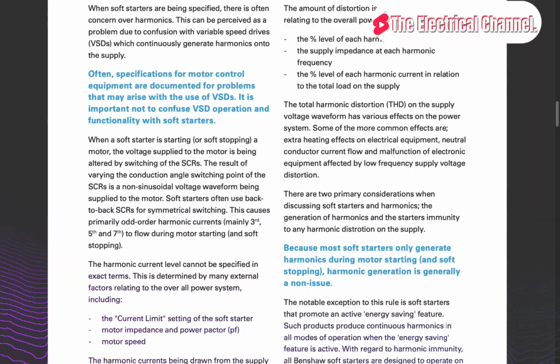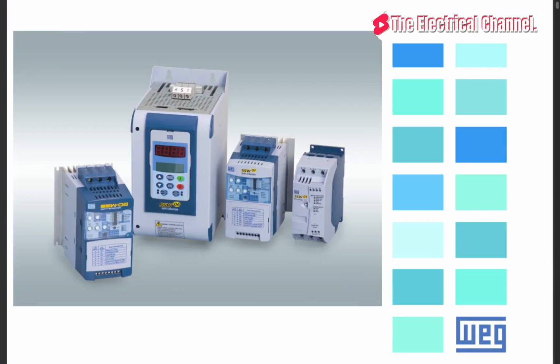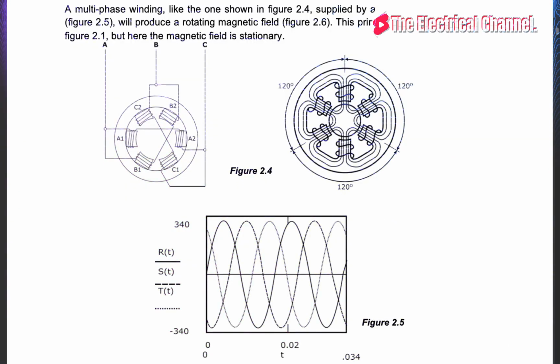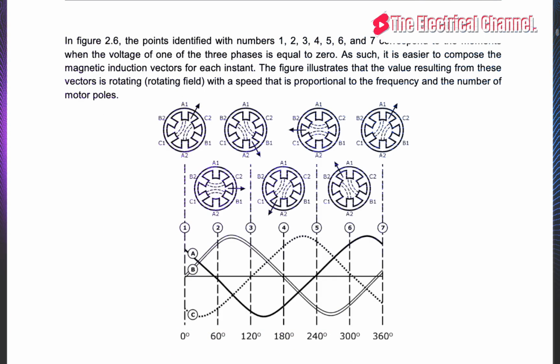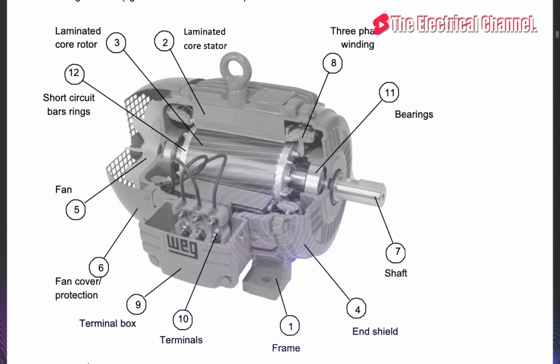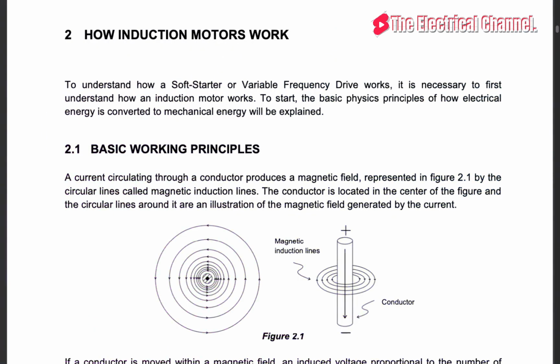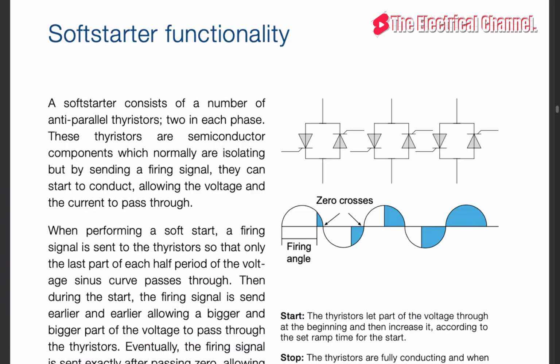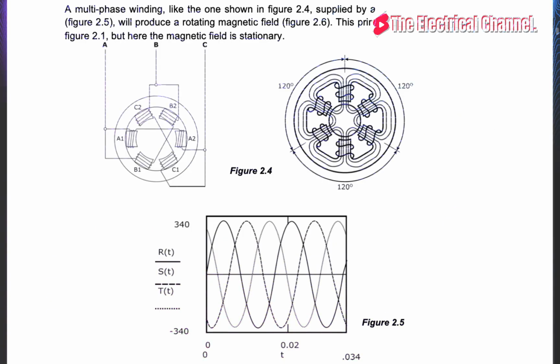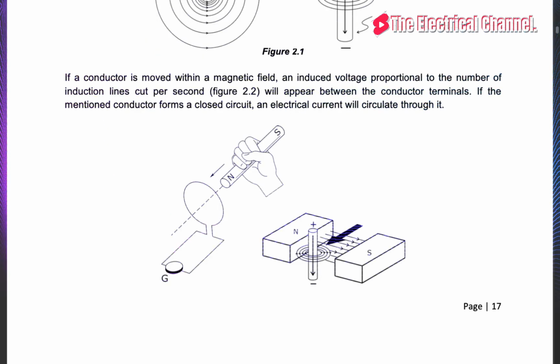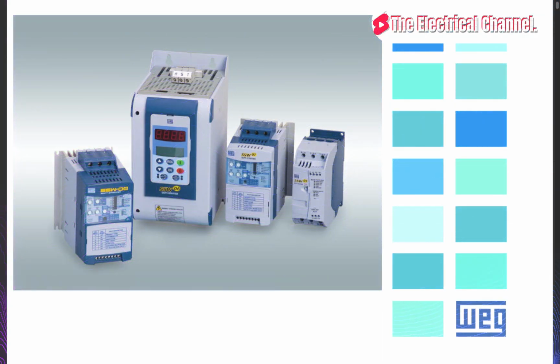Starting capacity and overload protection of a soft starter. Starting capacity of the soft starters. When starting a squirrel cage motor, there will always be a starting current, which is higher than the rated motor current. When first started, this starting current is typically 7 to 8 times the nominal current when starting a motor with a DOL, or direct online, starting method. This starting current is typically 7 to 8 times the nominal current, and when using a soft starter, it is reduced to 3 to 5 times the nominal current.